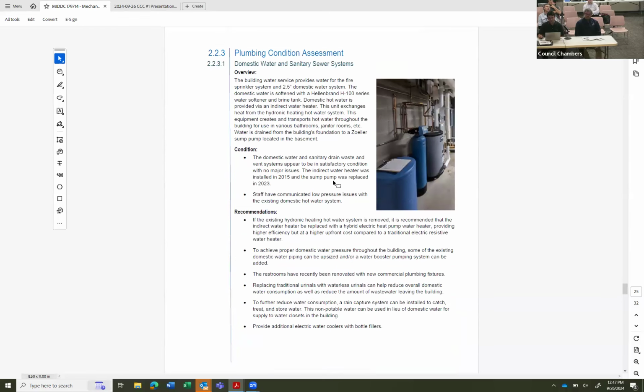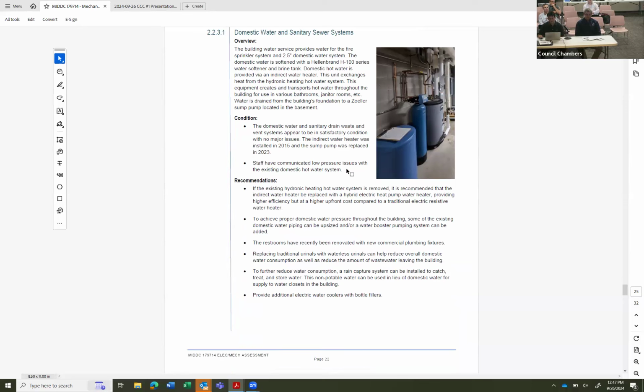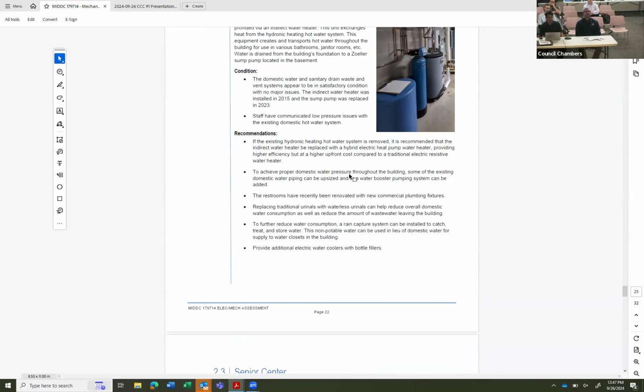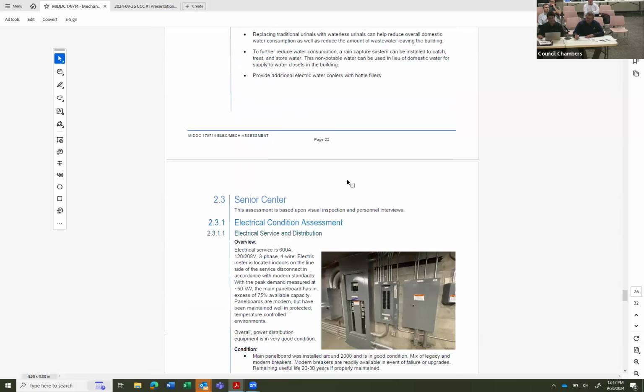And the plumbing systems appear to be in good condition overall. There are a few notes that the staff have communicated low pressure issues with the domestic water system. So I would recommend, if it's needed, a couple of things. The biggest step to improve that would be to install a booster pump to increase the system pressure, but it may just be as simple as redoing some of the piping and increasing pipe sizes to allow for more pressure in the system.